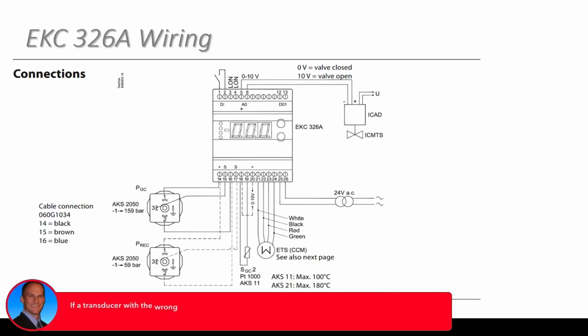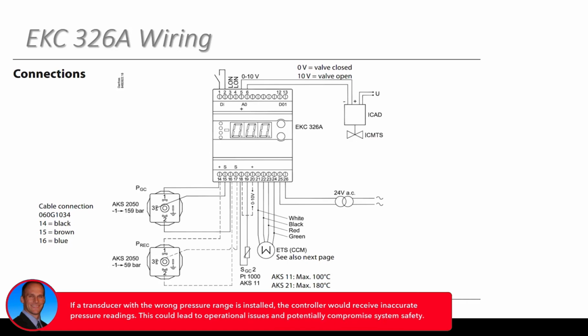In that case, you're reading a larger range than you think you are, and the voltage would actually be lower than what it should be, and so you'd be reporting a lower pressure back into the EKC because of that. So yeah, you would definitely see some issues with the receiver. You could blow a relief valve because the pressure's higher than what you think it is because of that transducer.